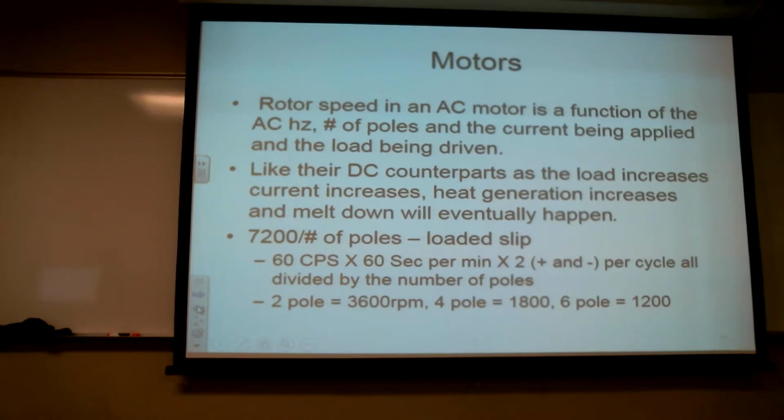And then you're going to grab it and load it. It's going to slow down. Counter-motive force is going to start declining. Induction occurring in the induction rotor is going to start declining. Current's going to go up to make up for it. So this thing could eventually get to the point that you probably won't get this hot enough to melt it, but the inciting AC windings that are copper wire wrapped with insulation or coated with insulation, that insulation will eventually get really, really hot. Okay?